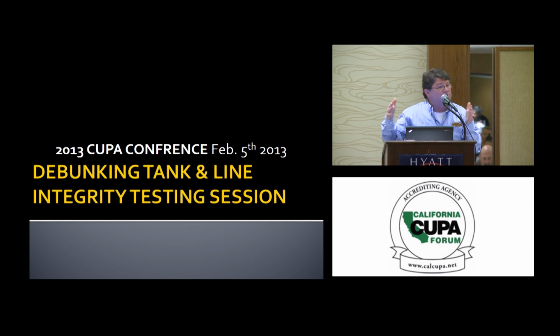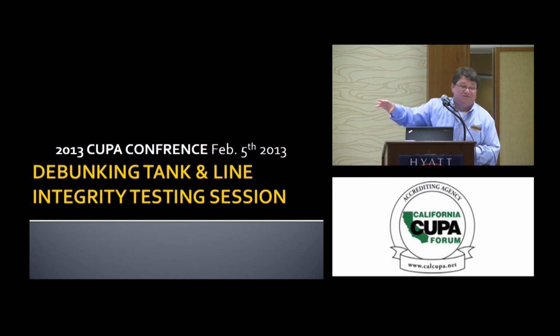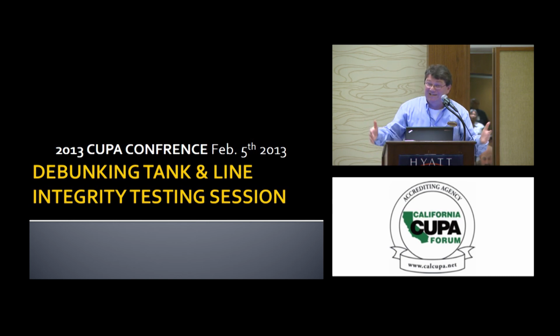Look, you want the right equipment in the right situation. When it comes to tank testing, find out what the physics are around the tank. If it's clay and water, you may have to use a different method. We have some stuff along the San Francisco coast I've been partnered to testing, and they said, Steve, when the tide goes out, we see this result. When the tide comes in, we see this result. They said, obviously, we need to test in those circumstances to find out what we're seeing. Why is that changing? Because obviously the physics are changing.